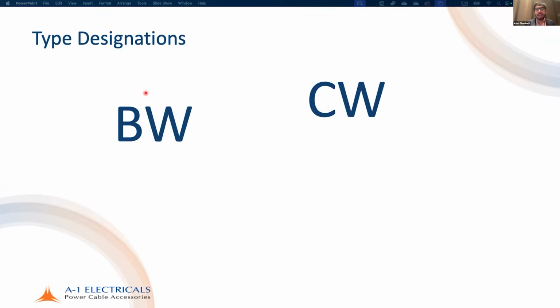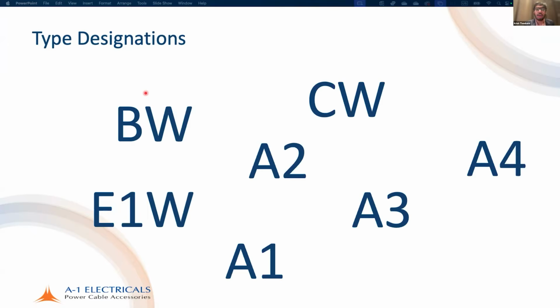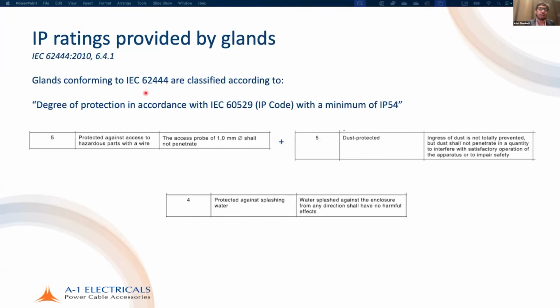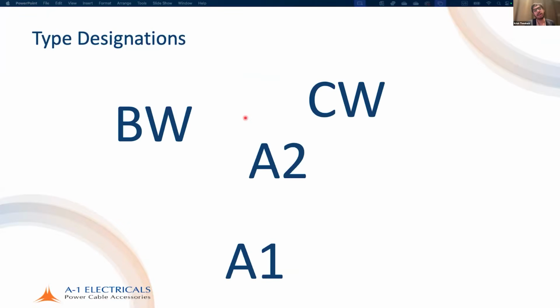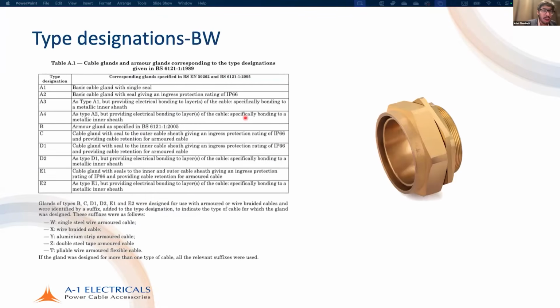For example, BW, CW, A1, A2, A3, A4, E1W. What do these mean? I'll go over this and explain. It's not always necessary to choose the most extreme type. Again, these are legacy codes, so you need to look at what the product conforms to. The important thing really is your 60529. So BW, CW, A1, A2, A3, A4, E1W are legacy codes. BW means it is an armor gland as specified in this standard, designed for single steel wire armored cable. This is an example of a BW gland.